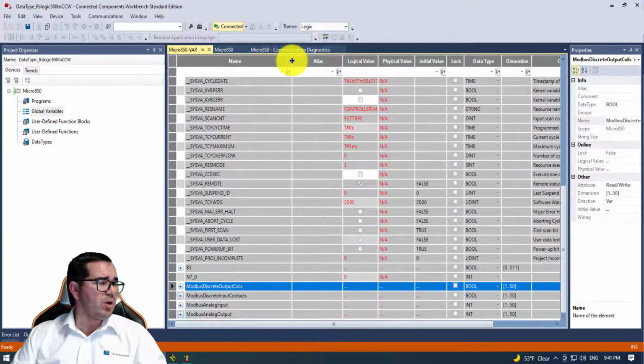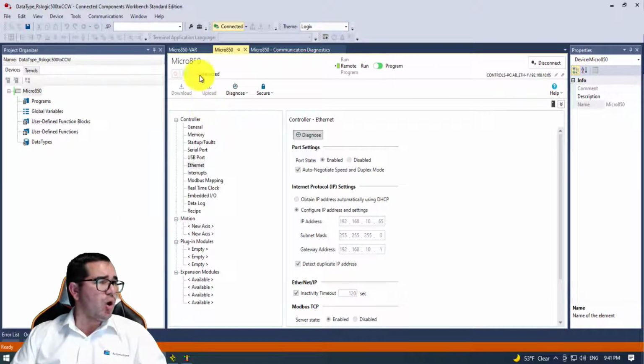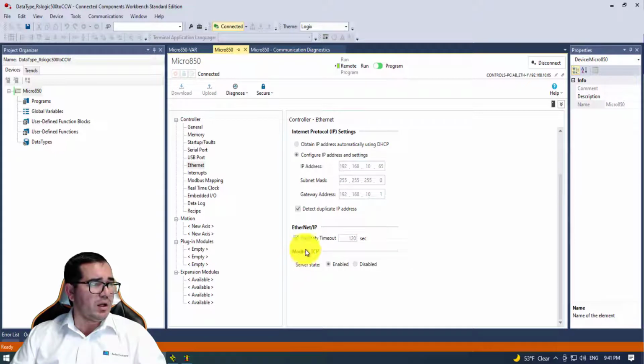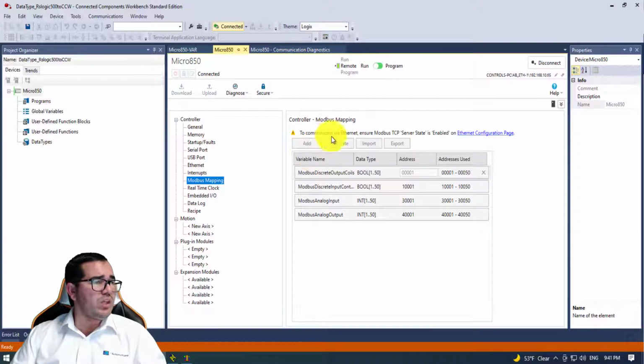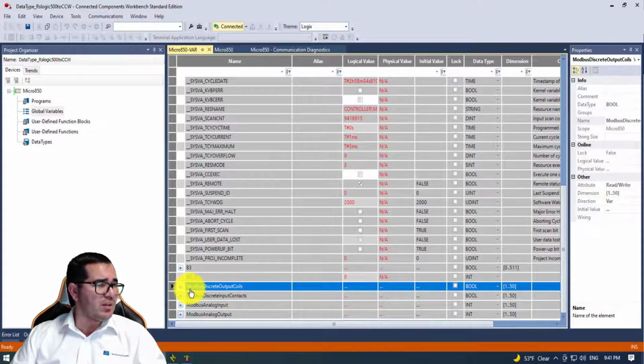What I did was I created these tags, but before you create them, you need to make sure that your Micro 850 or 800 family is offline, and you need to enable the Modbus TCP server state, like I put on mine. After that, go to mapping, Modbus mapping, click add, and you need to create these: Modbus discrete output coils, Modbus discrete input contacts, Modbus analog input, and Modbus analog output.